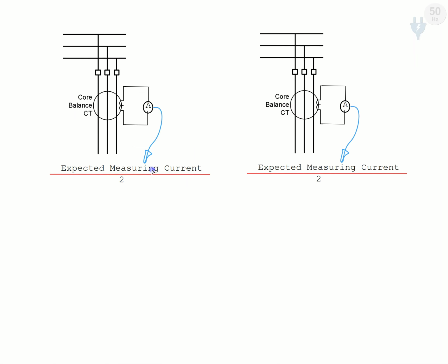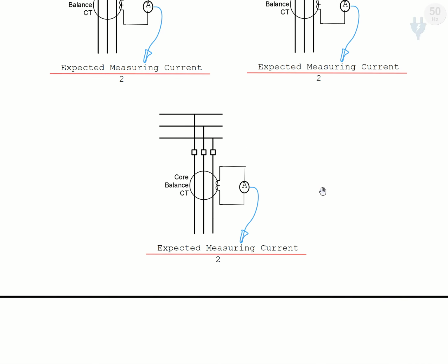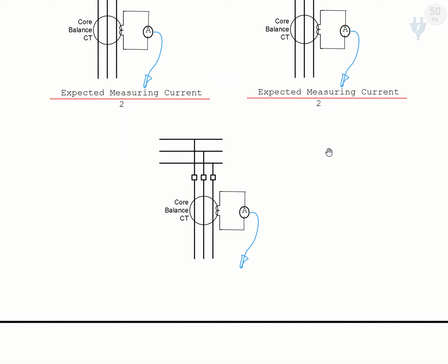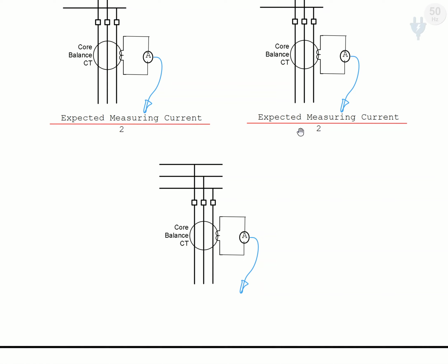And if we have our system isolated system, the same, we are finding what amount of the current will flow during the fault, the residual current of course, that amount we divide by 2. That is the minimum polarization current for direction determination setting.